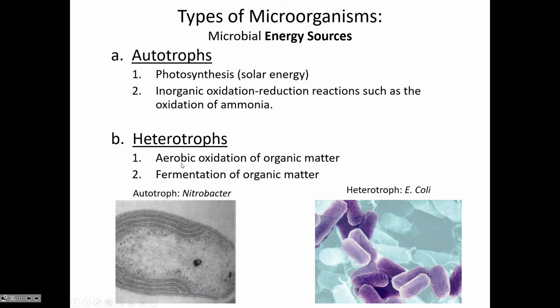But there's also a lower energy process. The fermentation of organic matter is in the absence of oxygen. They can gain energy from organic matter, and it's much slower and it yields less energy, and so you have to provide much longer exposure times to break down waste if it's being done through a fermentation process. But the heterotrophs that we will have growing in an aeration basin for activated sludge move very quickly, and then typically we'll use fermentation during sludge treatment.